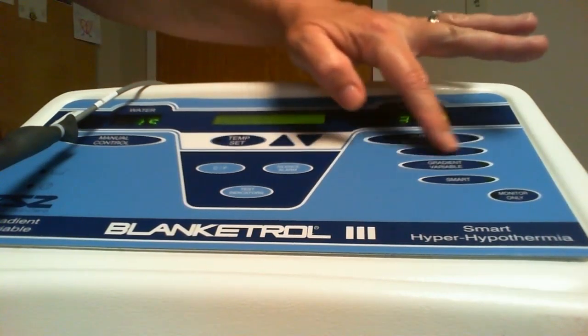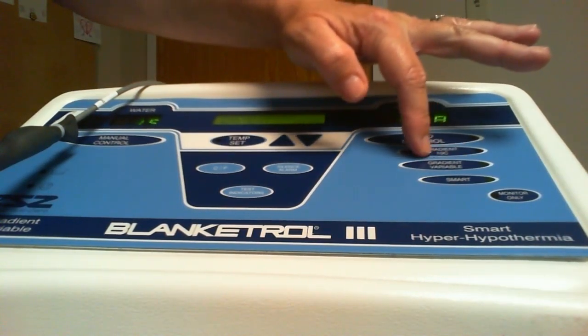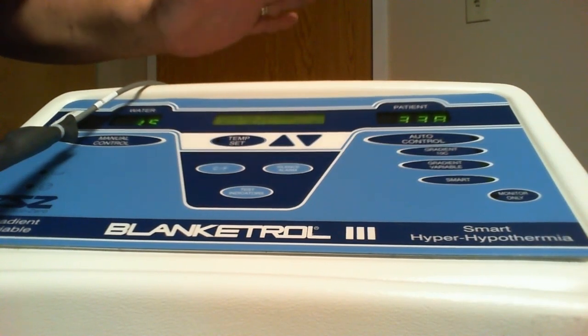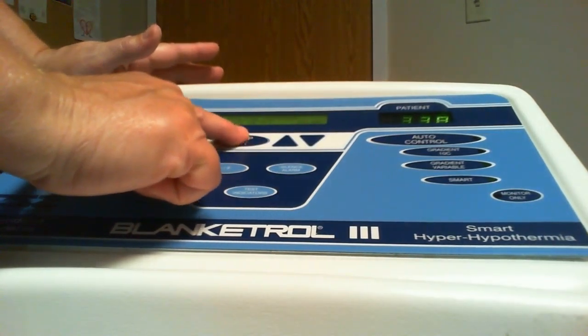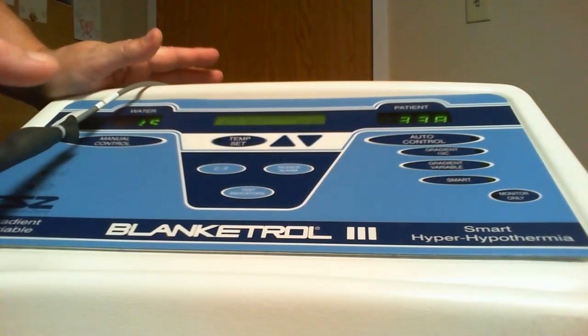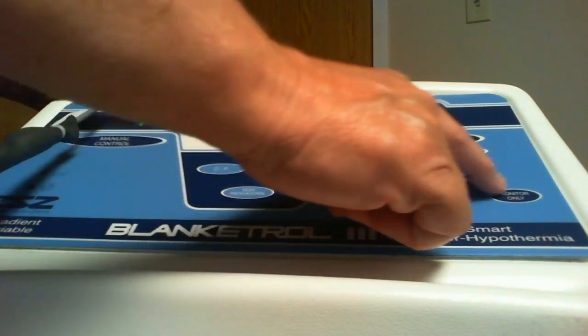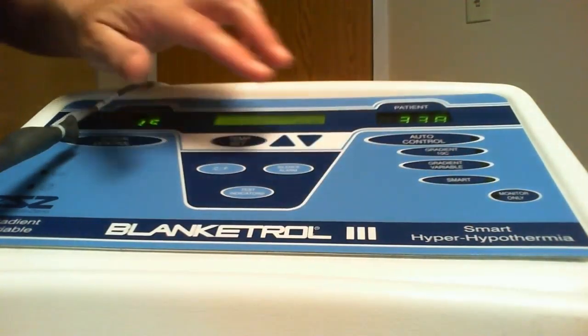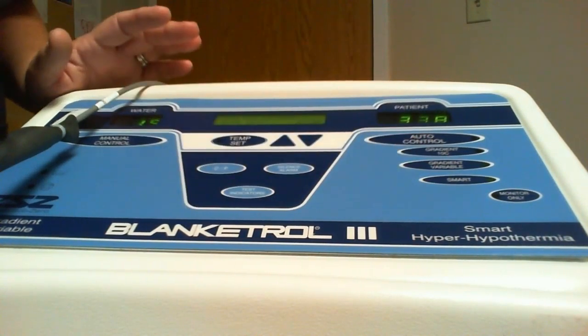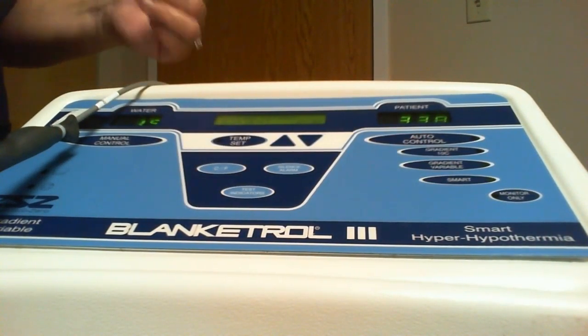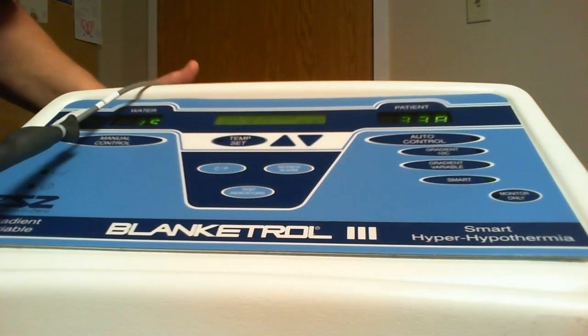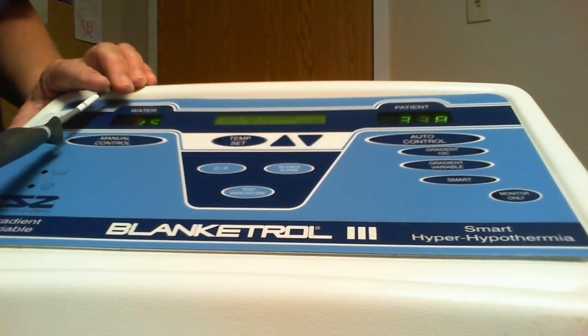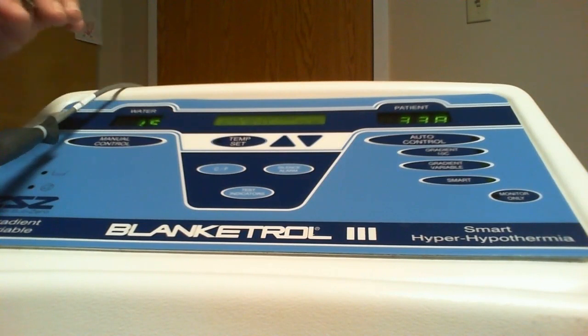So there's a gradient 10, which is what we use on most patients. But if you're not able to achieve that temperature, then you would hit the temp set button to stop it, go to gradient variable, and you would manually put the temperature offset into the machine. Always use the smart mode when you're using gradient 10 or gradient variable. It just is an extra eye on the patient, keeping tight rein.